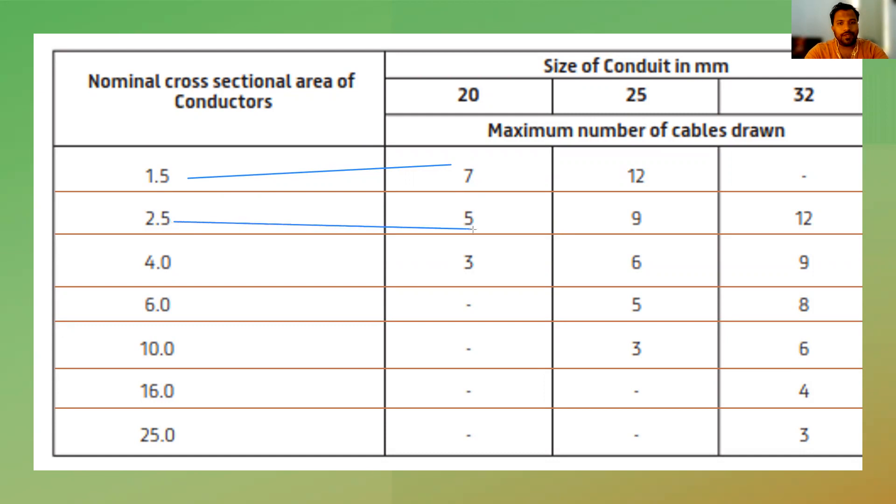Similarly, for 2.5 mm wire, you have 5, and for 4 mm, you have 3. Similarly, for 25 mm conduit, for 1.5 mm wire, 12 wires can be drawn, for 2.5 mm, 9 wires, and for 4 mm, 6 wires.